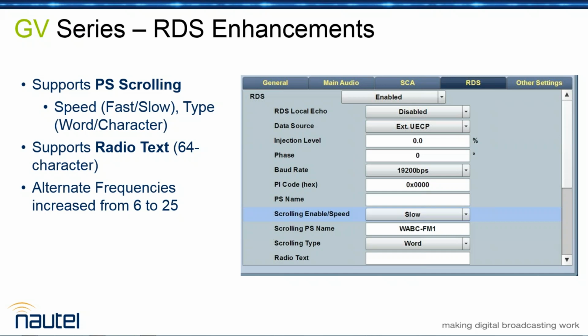Every automation system has a control engine of some sort, or a control manager, where you can go in and set how often it sends the data. The other most common thing I see is folks forgetting that they have to set the port number - they can't just point the automation to the transmitter IP address without telling it specifically what port to send the data to, and that is in the book. It's 7005, for anybody that doesn't know. But those are the things I see most commonly.